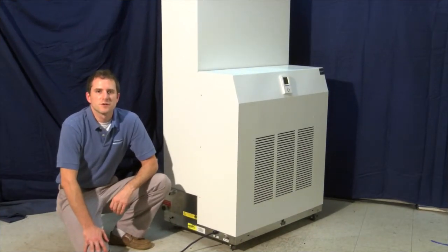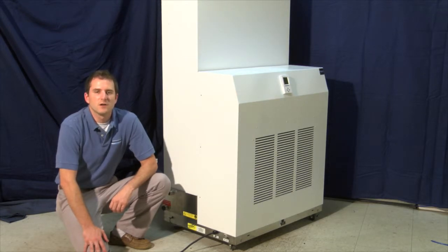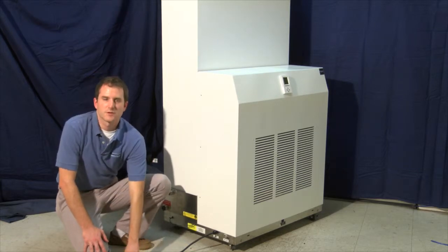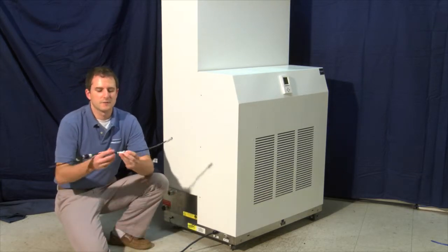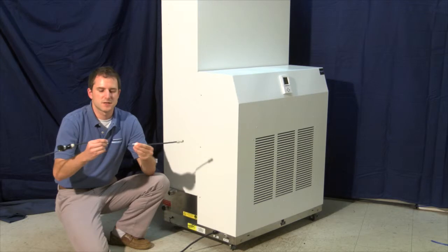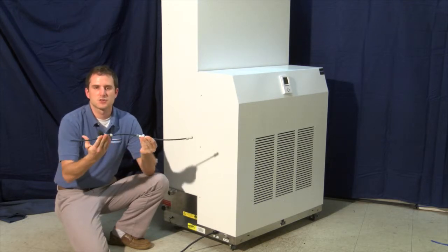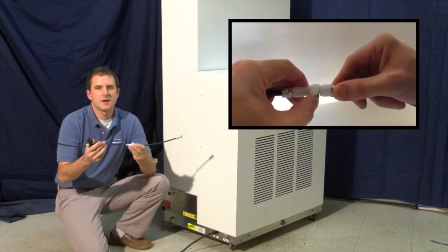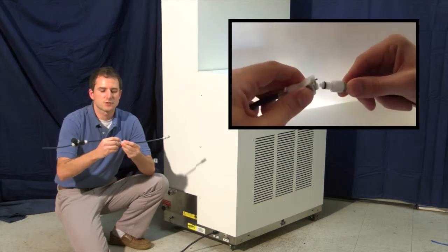All of Humidifirst ultrasonic humidifiers require a plumbed water source. Generally, we recommend treated water such as reverse osmosis or deionized, although there can be specific scenarios where treated water should not be used. All of our humidifiers will ship with a 1/4-inch water line with male-female disconnect and attached Y strainer. This will allow you to quickly disconnect the water source.